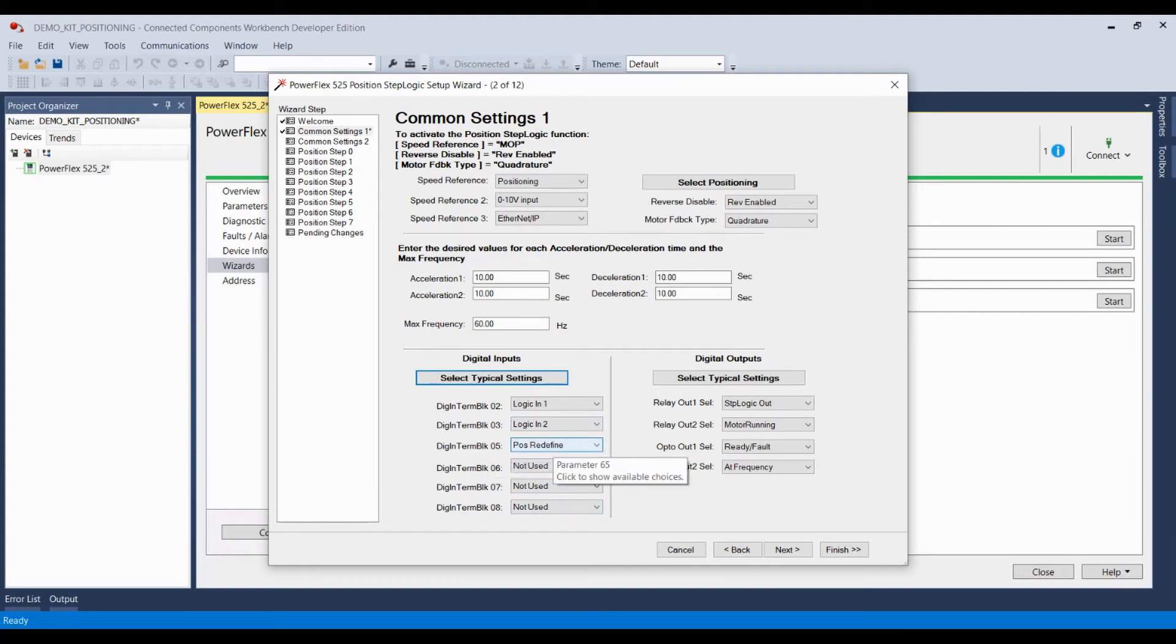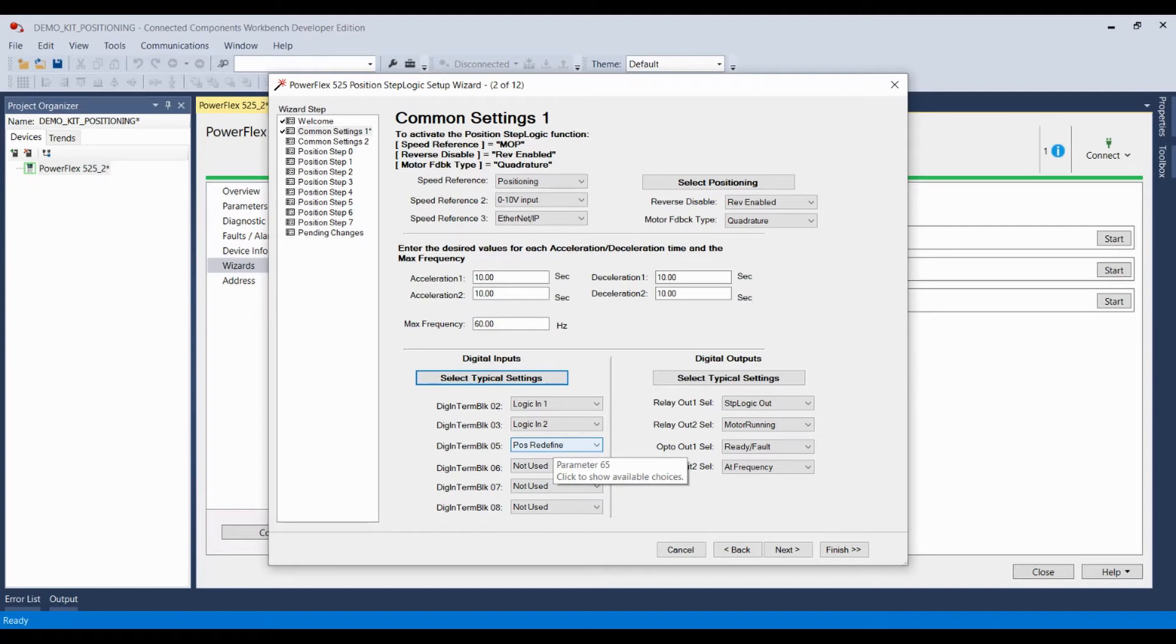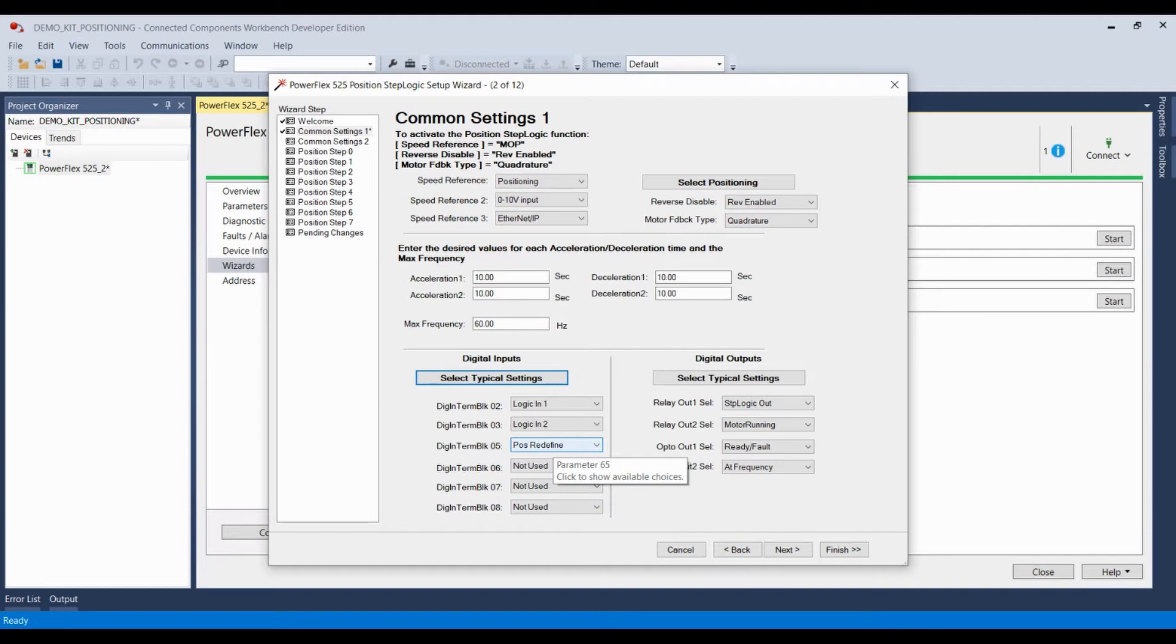And for digital terminal block five, I have set as position redefine. Position redefine allows you to use a digital input to tell the drive that it's in the home position. This is something that's very useful if you're using absolute. If you're using absolute positioning, if your drive is powered down and powered up, you're going to have to rehome the drive, and you're possibly going to have to rehome the drive after a fault has occurred, or if you auto-tune the drive again. So having a quick button to set home after you've jogged the drive into position is very, very useful.